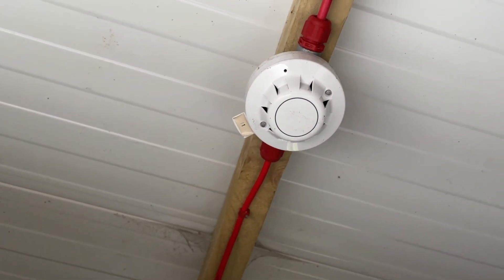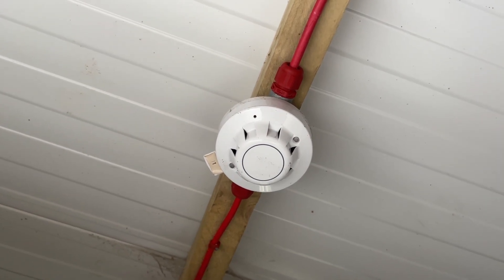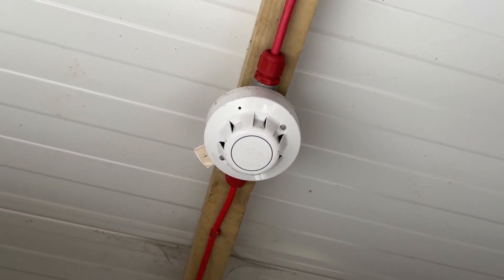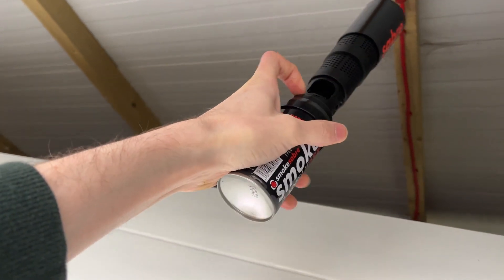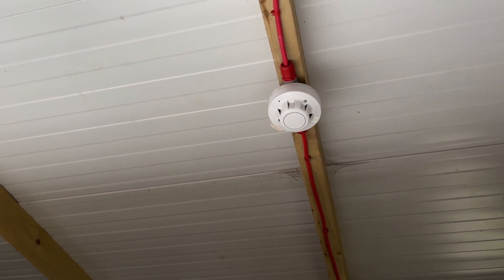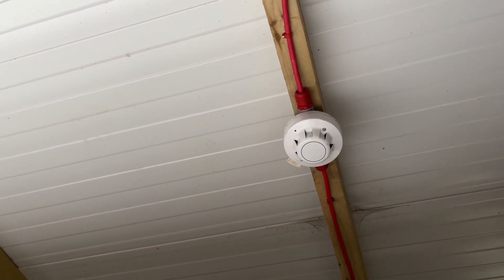Two scoots. Yeah, that isn't even triggering on pre-alarm, so alright, needs more. Come on. There we go — see, that's working fine. There's nothing wrong with the wiring out here.